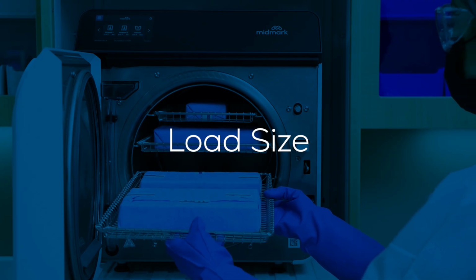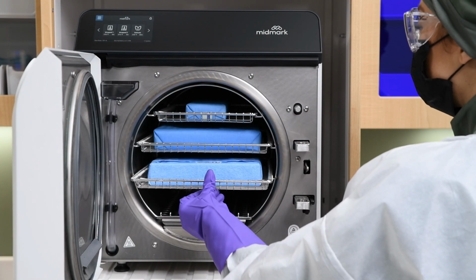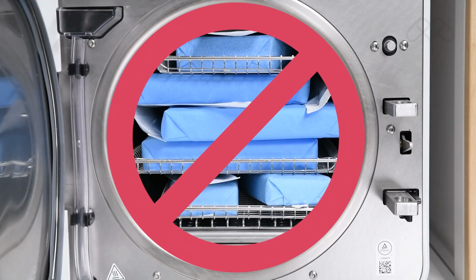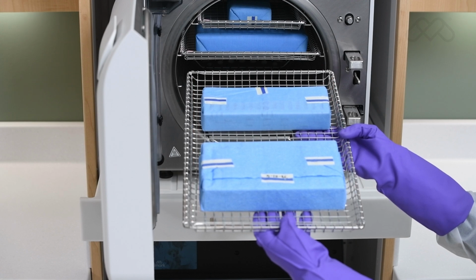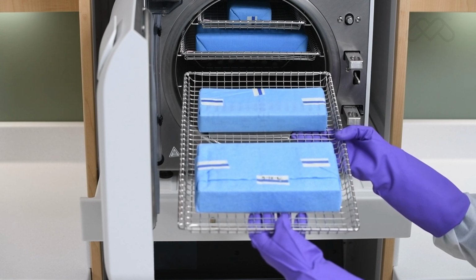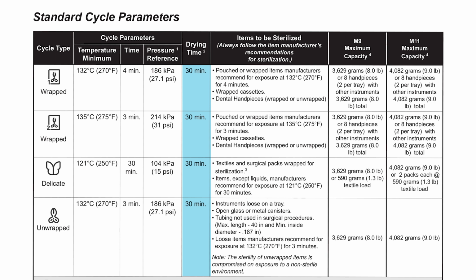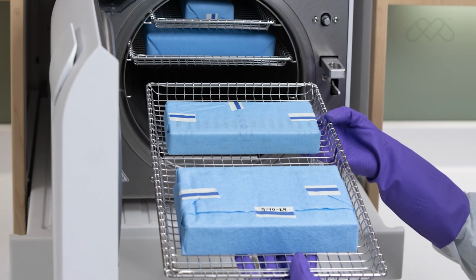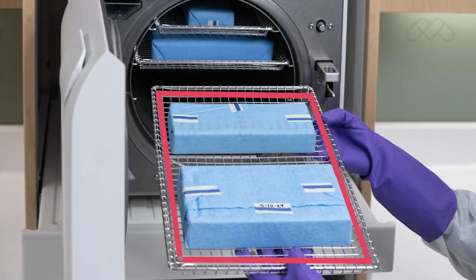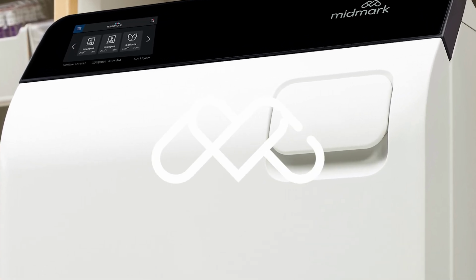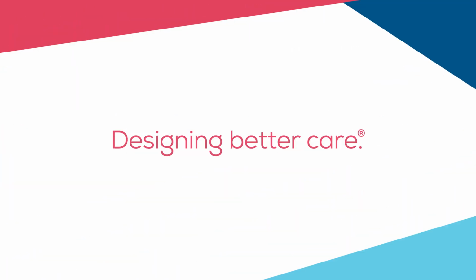Load size. Successful sterilization depends on proper loading of the sterilizer. Do not overload the sterilizer chamber. Adequate space must be maintained around all items placed in the chamber to ensure proper steam circulation and adequate drying. This chart provides guidance on the maximum loads that can be processed. Maintaining proper spacing between all items being sterilized should be the deciding factor in determining the maximum load that can be processed. For more detailed information about your sterilizer, refer to the Midmark Steam Sterilizer Setup and User Guide.